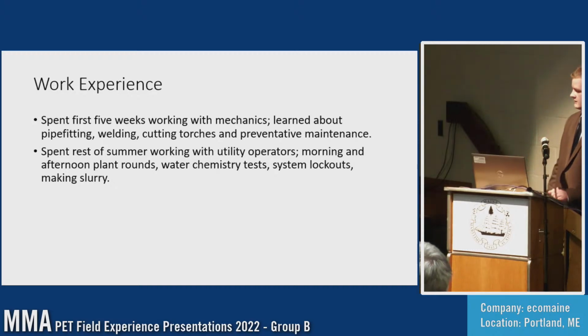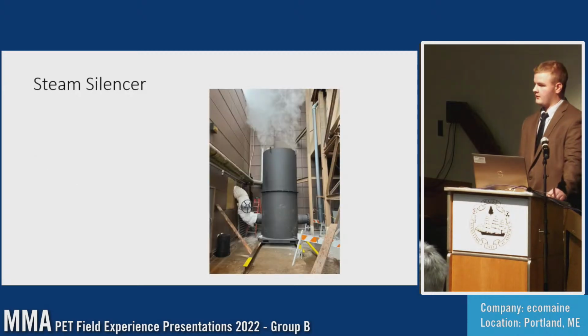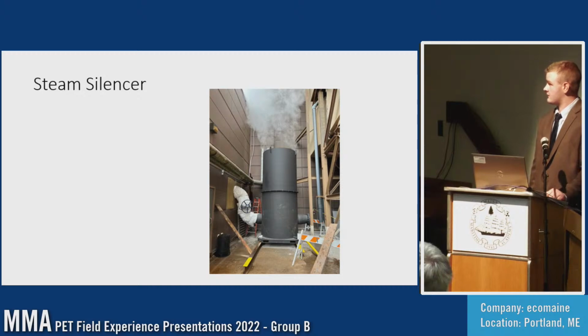Because of the reduced loads this summer, without a turbine we were unable to run at full load. We were running at about half load all summer and weren't burning enough trash. We ended up having to bypass at the landfill, which was costing the company a ton of money. So we installed a steam silencer that they rented, to dump steam so we could run at full capacity and burn - we about doubled our trash throughput.